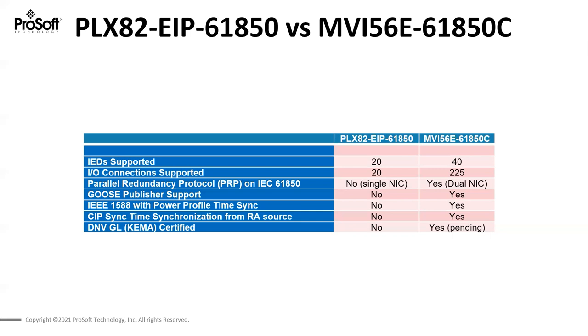GOOSE Publisher allows us to push data from ControlLogix directly to the protective relays. Previously on our gateway module we were only doing that with hardwired IO. We also support IEEE 1588 with the power profile, which allows us to synchronize those protective relays. Since we also support CIP Sync Time Synchronization, it is now very transparent to pass from CIP Sync Time Synchronization over to 1588 with power profile support.